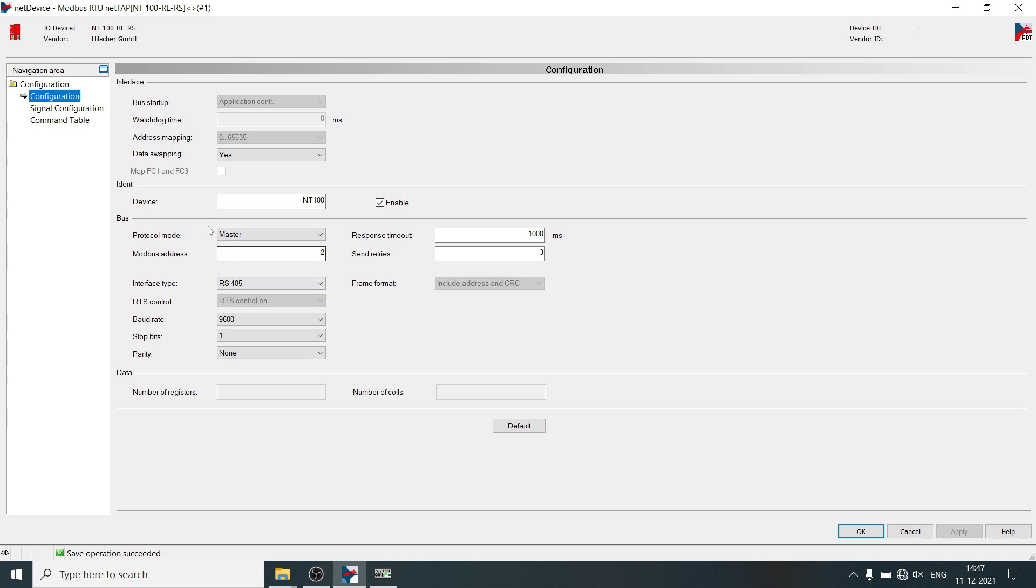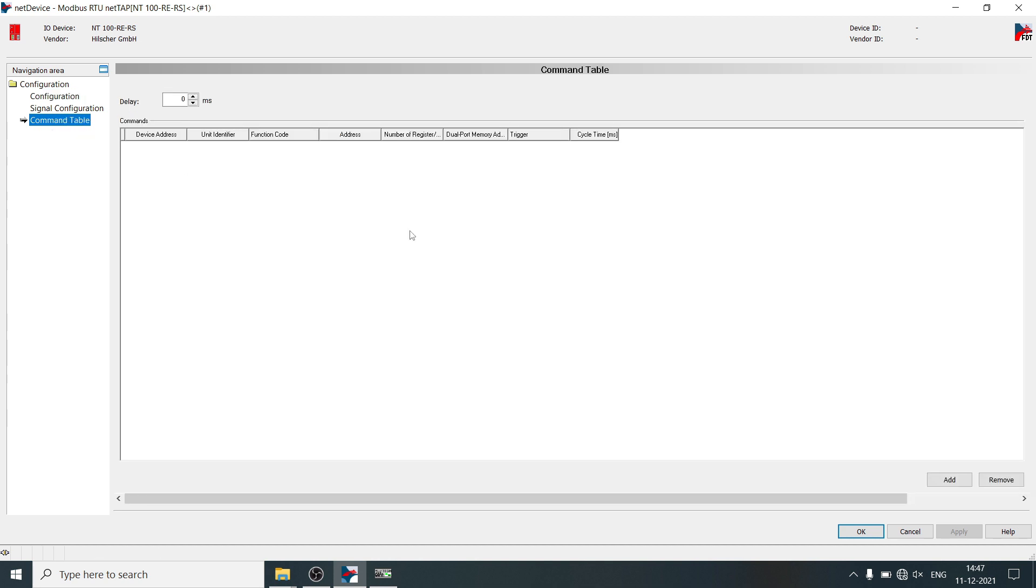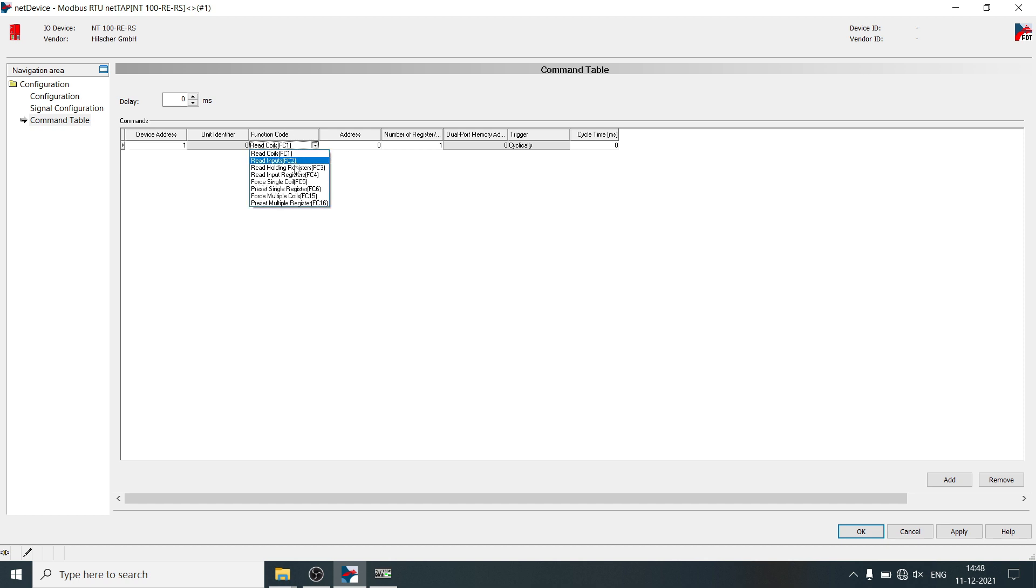Select command table, click on add, define node address of the energy meter, select function code as read holding register, define parameter address.